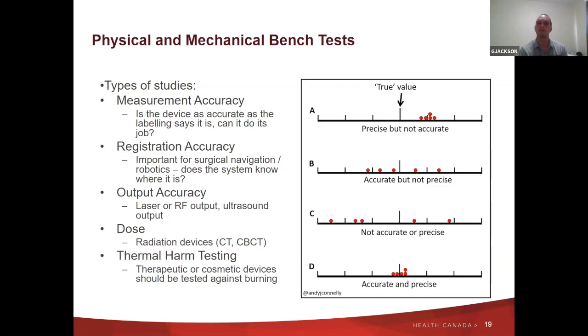Thermal harm testing is something we see. Health Canada has a guidance on this for especially therapeutic and cosmetic devices that use laser or RF or things. Their mechanism of action is typically heating the tissue, but we want to see that it doesn't overheat the tissue and cause burns.